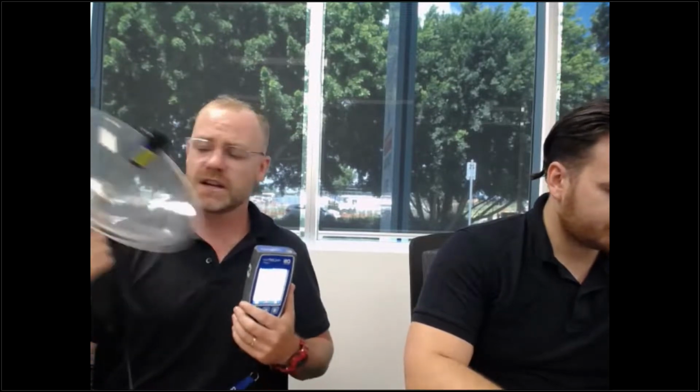For that, what would technically happen is you would probably get a massive pulse of electromagnetic energy that you can pick up via the TEV, and a massive pulse of sound that you can pick up via your ultrasonic dish. It would be very short-lived, and you may not get a good recording of it because it happens so quick. Your volts are on, the power's on, and then the volts are off. So it's probably not the best application of the instrument.